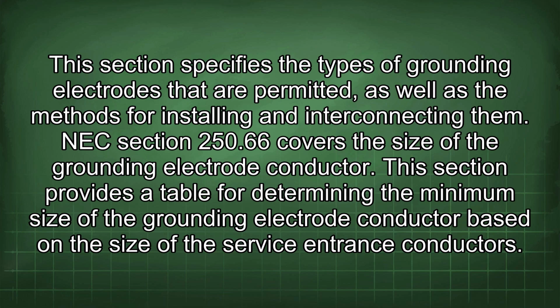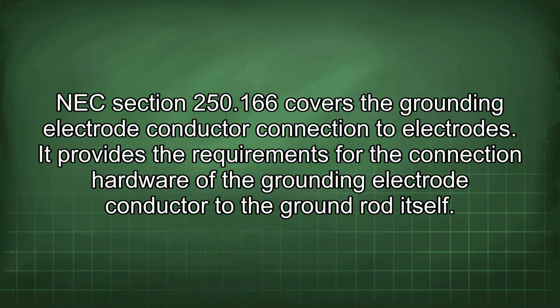NEC Section 250.66 covers the size of the grounding electrode conductor. This section provides a table for determining the minimum size of the grounding electrode conductor based on the size of the service entrance conductors. NEC Section 250.166 covers the grounding electrode conductor connection to electrodes. It provides the requirements for the connection hardware of the grounding electrode conductor to the ground rod itself.